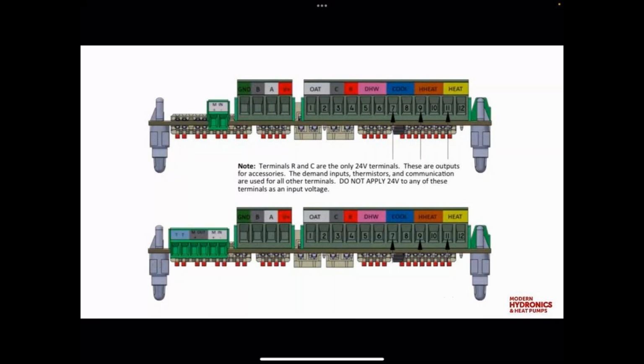So looking at some of the questions here, Ryan asked that the set point on the DHW was showing 135, and he asked how high the heat pump takes it before backup takes over. We allow you to set the screen up for 135 degrees. We will overshoot that. Technically, we'll allow it to go up to 140. But the backup really isn't a function of water temperature as far as overshooting a certain water temperature. It's whether or not the compressor is running at 100% and can't reach the target temperature that's being asked for in that moment.